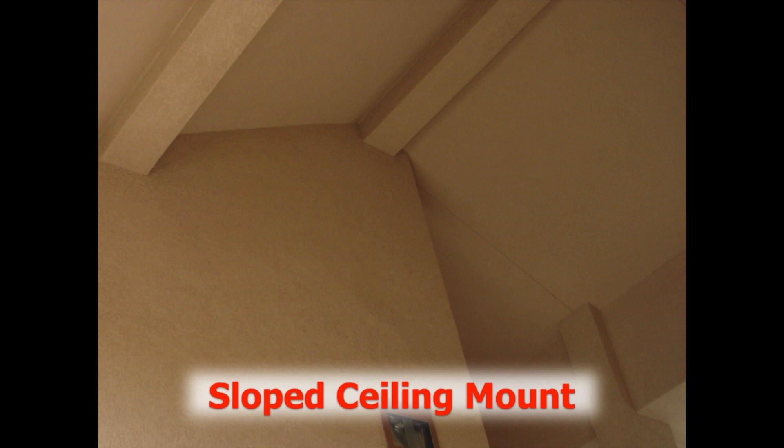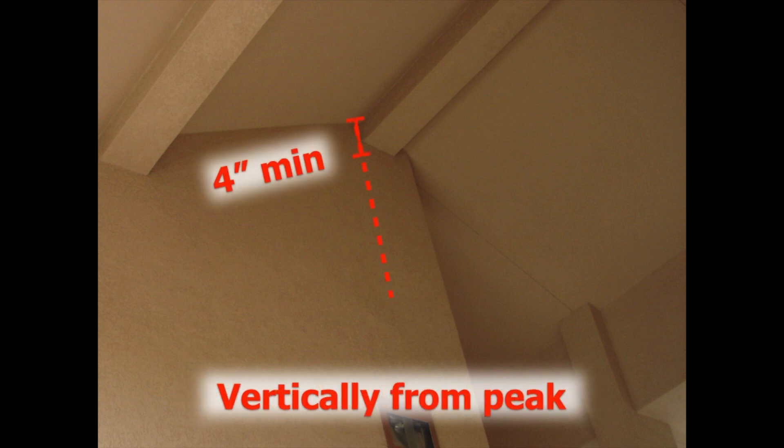First, if we look at sloped ceiling mounts, smoke alarms cannot be closer than four inches vertically from the peak where there could be dead air movement and the smoke may not reach that area to trigger the alarm. We'll shade in this region where alarms could not be installed on a sloped roof.